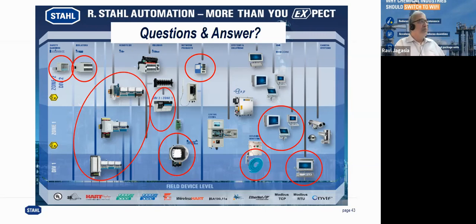One was, what is the difference between flameproof and explosion proof? Let me answer that. Basically, explosion proof is covered under the NEC 500, the NFPA standard. The flameproof is under the IEC 60079. There are certain construction specifications and testing requirements which differentiate both of them. And it's a very short platform here to go into more details, but I hope this helps. The concerned audience member can definitely write back to us and we can support them.